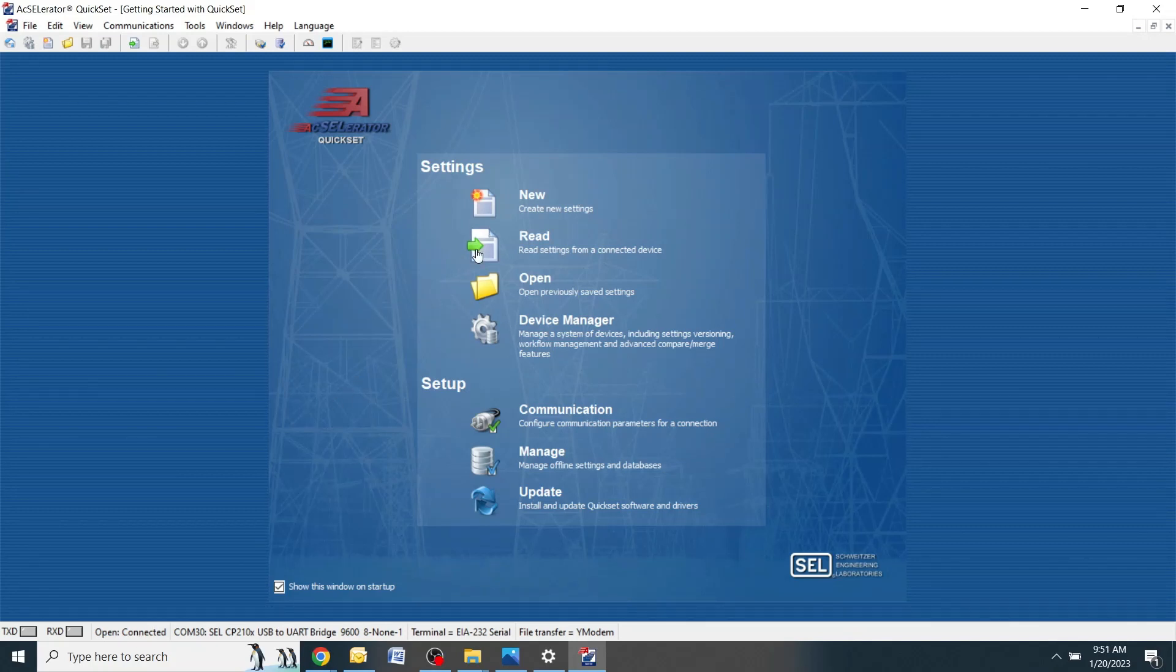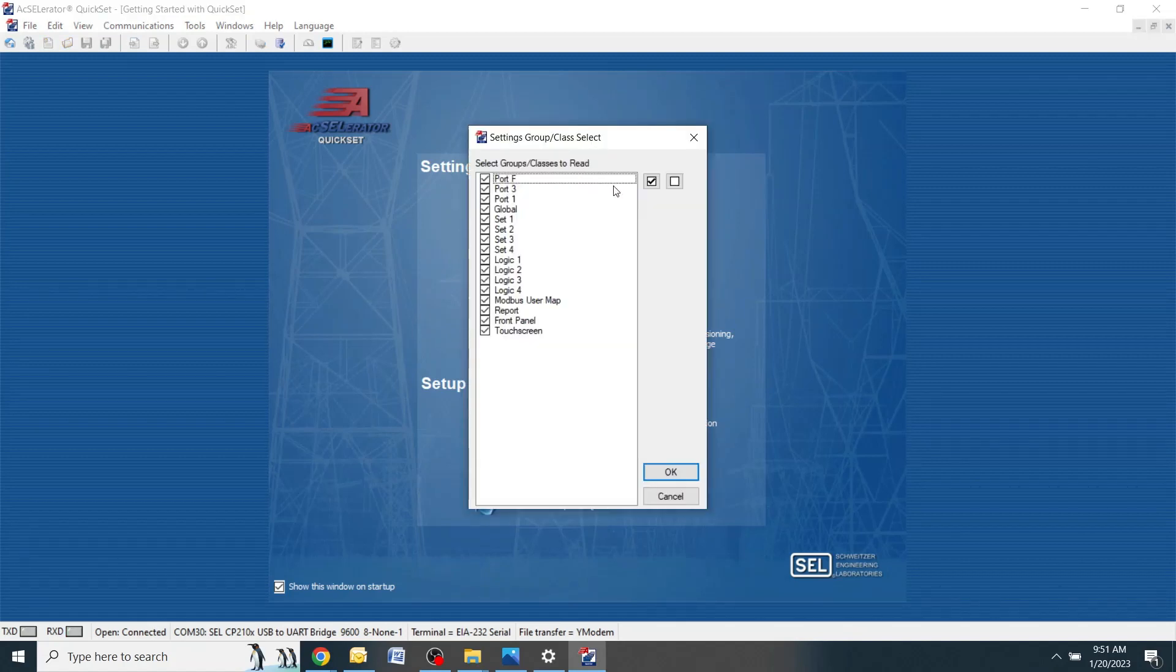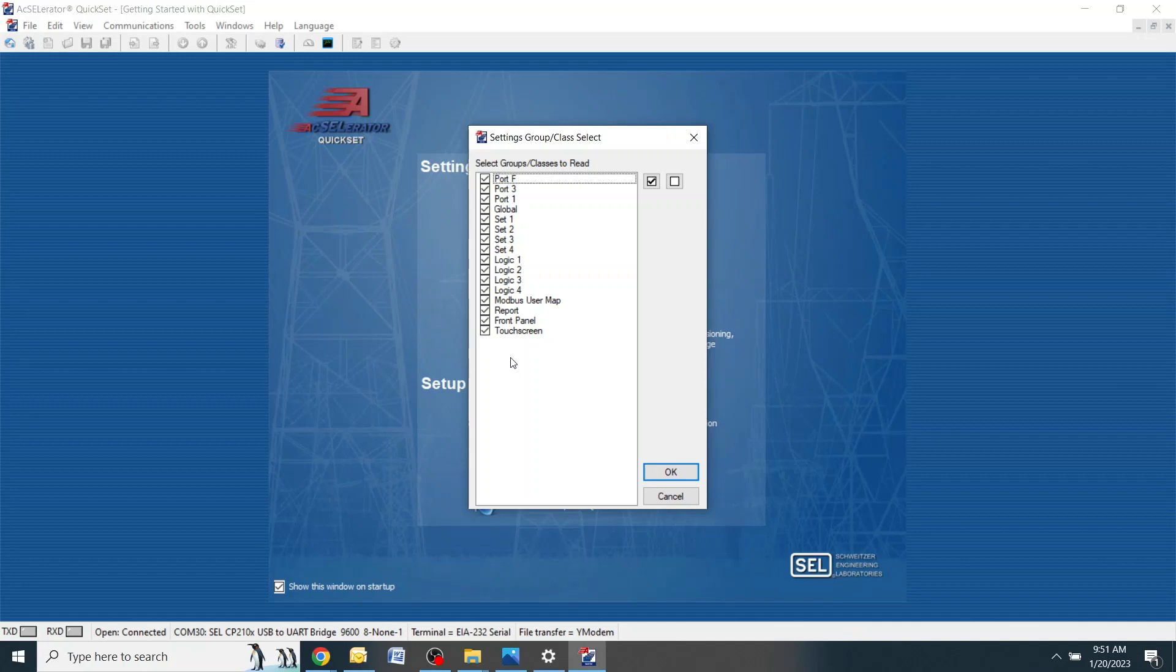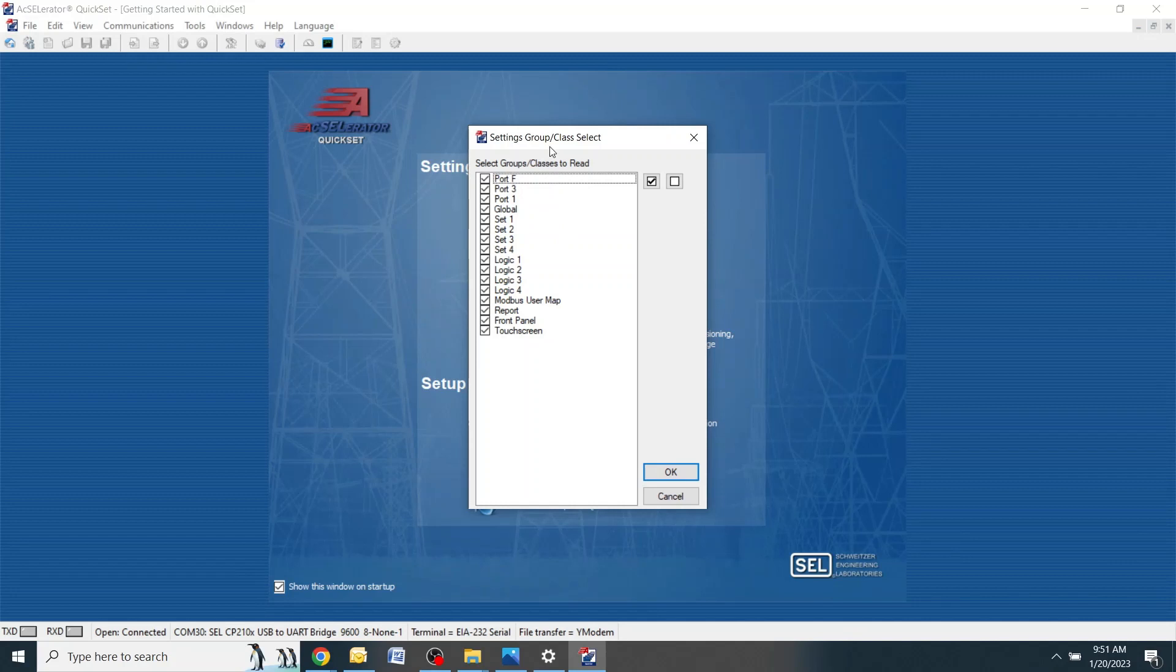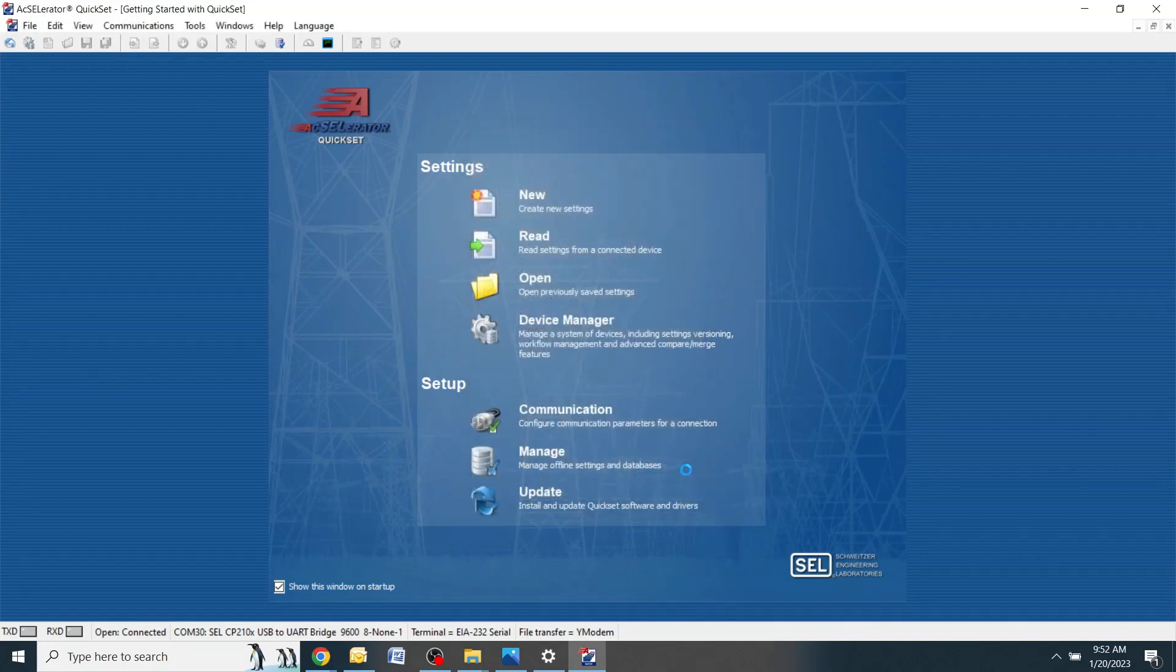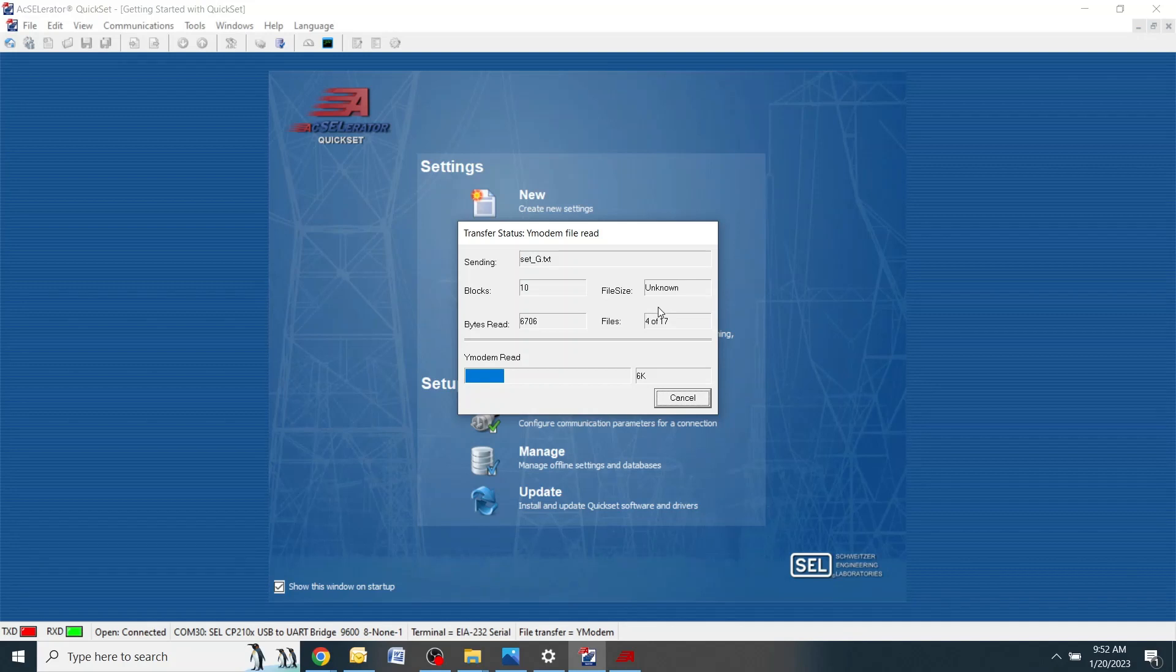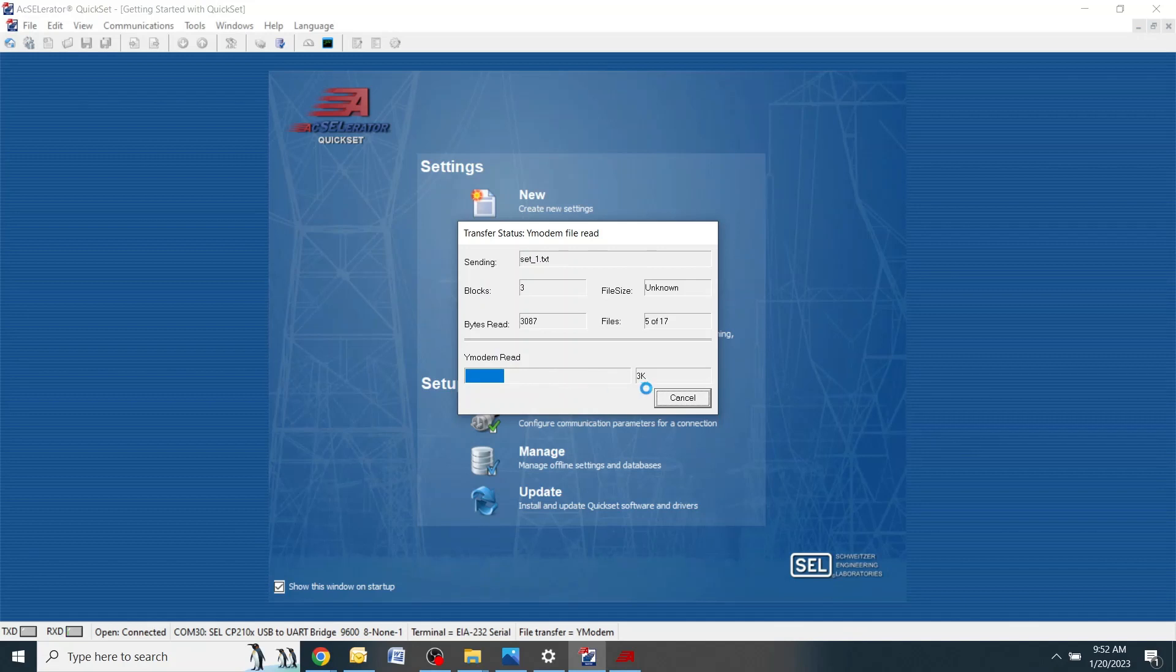To read the device settings, next go up and click read. In most cases this screen will pop up and ask you which device ports and settings you'd like to read from. It defaults to all of these selected. You can leave them all selected for right now so that it grabs all of the information out of the relay. Once these are all clicked off, click OK. At this point the computer is downloading the information out of the relay. This can take quite a bit of time, five to ten minutes in some instances. You want to leave this alone, don't touch any keys at this point.